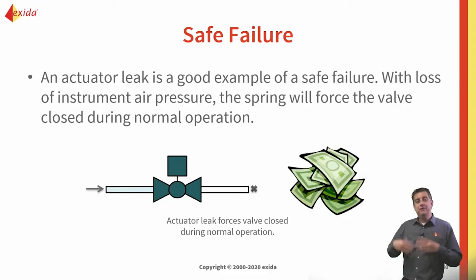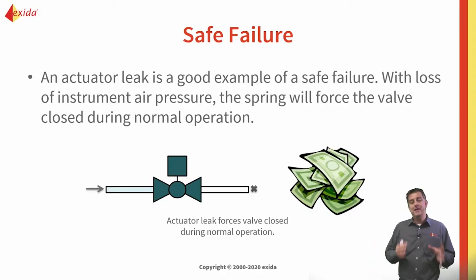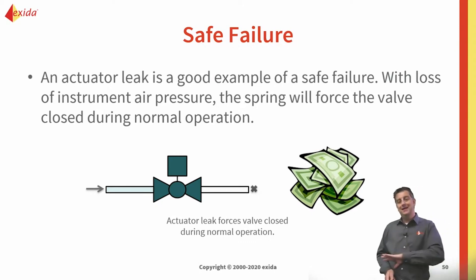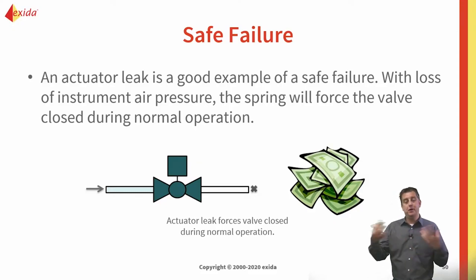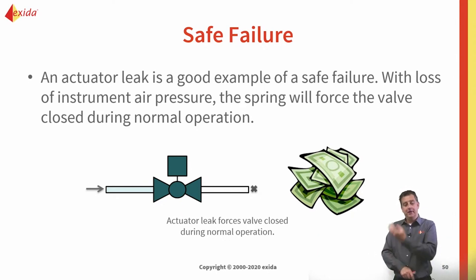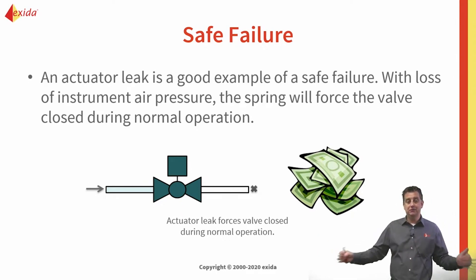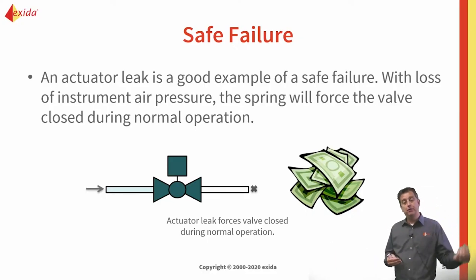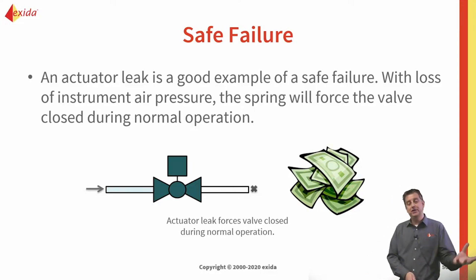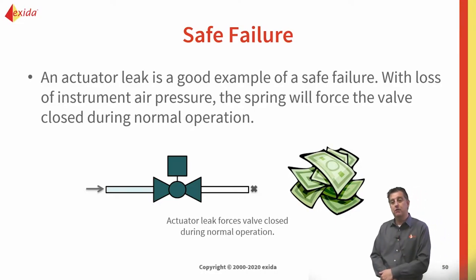In functional safety, we're really focused on dangerous failures — making sure our safety instrumented functions perform when they need to. We tend to somewhat neglect safe failures, but any production manager or organization will say they don't want a spurious failure every day. In our simplified equation we only look at dangerous failures, but our calculations do compute both the probability of failure on demand as well as the mean time to fail spurious — giving an indication of how often the safety function may cause an unwarranted transition to the safe state.